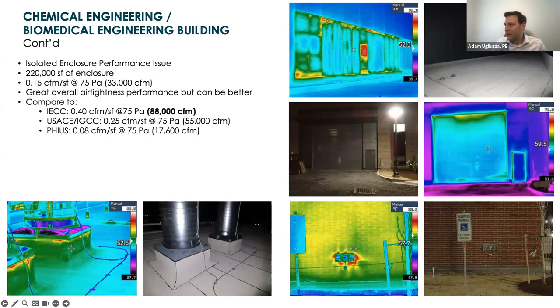So this was more of isolated spots. The general enclosure was pretty tight. The exterior walls and the roof, aside from the roof penetration, we didn't have a lot of leakage sites, and we did really well, 0.15. But just look at the difference between what you're allowed to leak and what we leaked in a building this size. We came in at 33,000 CFM. If we were going for code, we could go all the way up to 88,000. That's a huge amount of air leakage. You could have that overhead door wide open and probably pass. So just something to keep in mind, to give you a frame of reference here.